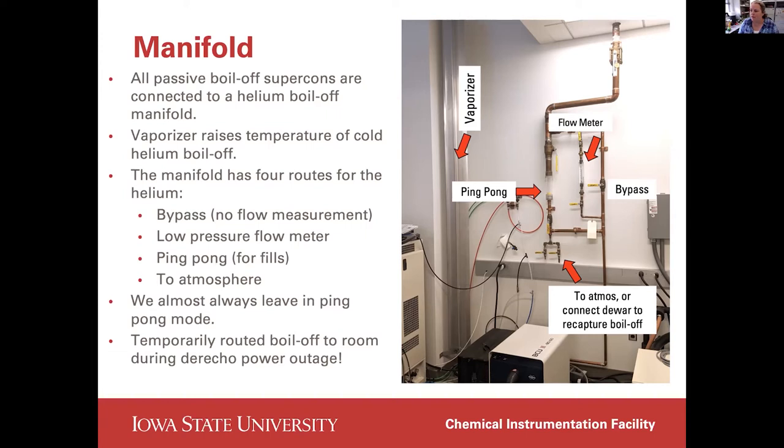This is pretty much the same setup for all of our magnets. The helium first passes through this vaporizer that you can see on the left here. That raises the temperature of the helium, and then it comes through the manifold where we have basically four routes it can go through.